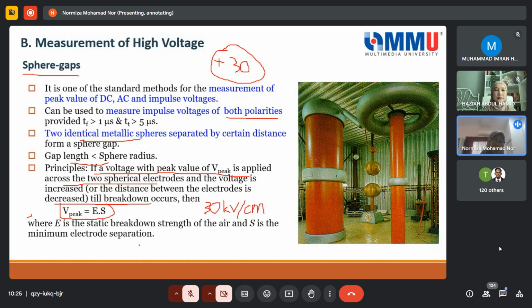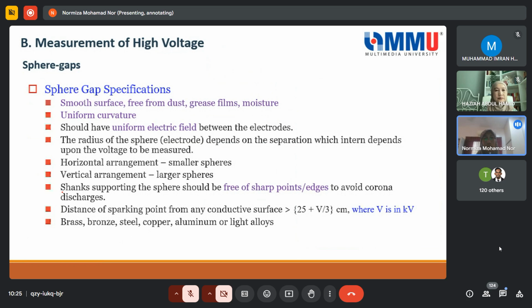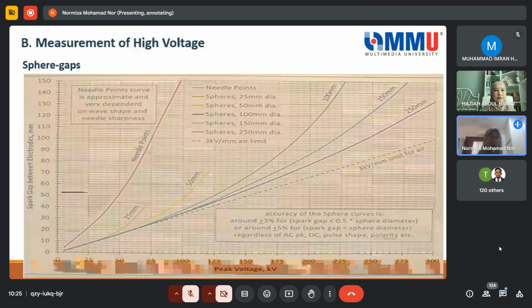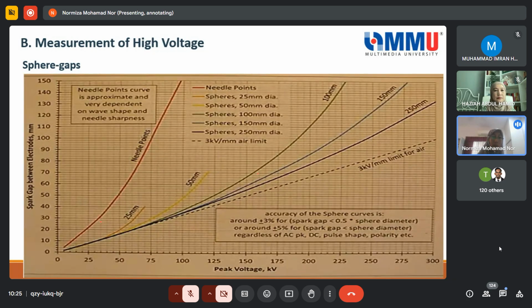If you measure 100 kV, maybe the distance is smaller. But if the voltage is increased, for example to 150, then the distance should be higher. You can see that relation, which I will explain. I think I have the graph here later on. When you want to measure a voltage of 150, you have to increase the distance between the spark gap. So for higher voltage, the distance would be higher as well.